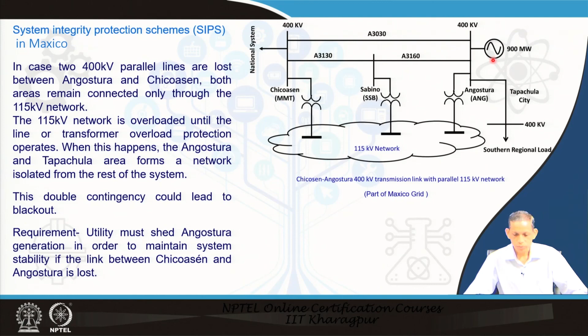We see here that we have a PMU placed at this end, and we have a PMU at this end, through available relays and with GPS facility. Now, this PMU sends data information to this one in real time through the communication system, and the corresponding voltage data here and voltage data here, they align, and then from the alignment the processor here sees what is the angle deviation between this side and this side.